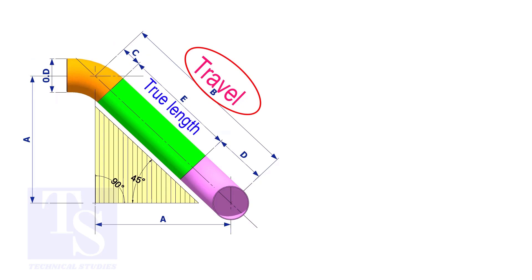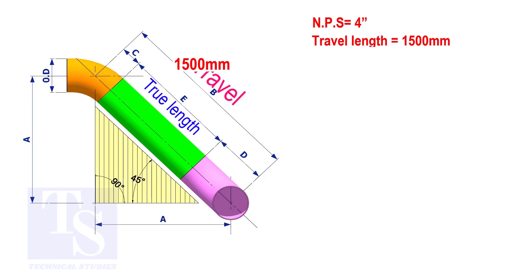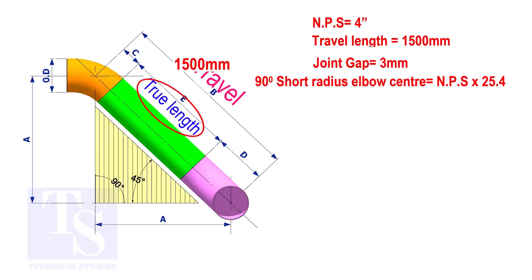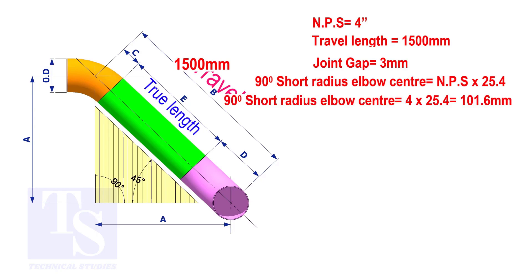Assume that the elbows are short radius. Nominal pipe size is 4 inch. The travel length is 1500 millimeters. The joint gap is 3 millimeters. To calculate the elbow center of a 90 degree short radius elbow, multiply the nominal pipe size by 25.4. The answer is 101.6 millimeters.